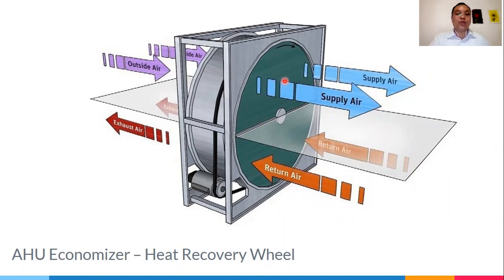So that's one effect of the heat wheel or economizer. Now instead of your cooling coil cooling from 34 degrees to 12 degrees, you're now only cooling from 28 to 12 degrees. That's a lower delta T, and because of that lower delta T, you require lower energy consumption. The difference in energy consumption is saved because of this heat recovery wheel.